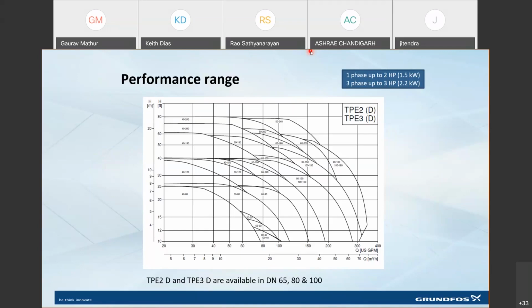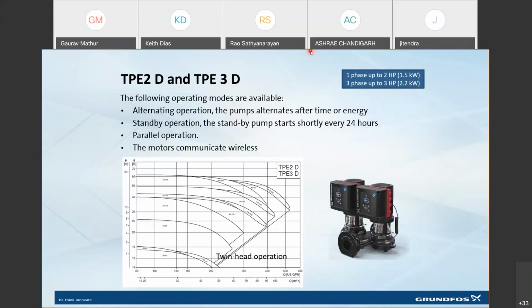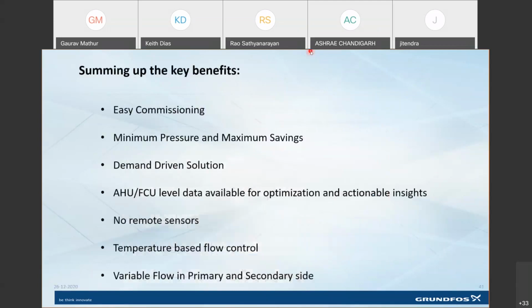You are able to achieve much higher heads, to the tune of around 24 to 25 meters as a maximum head, and a flow of around 75 meter cube per hour, which primarily covers most of the commercial buildings. But if your requirement is higher than that, you can consult with Grundfos, and we can work out a solution for this. We have already discussed the twin head pumps, so I will just move ahead and go to the summing up of the key points which we have discussed today.